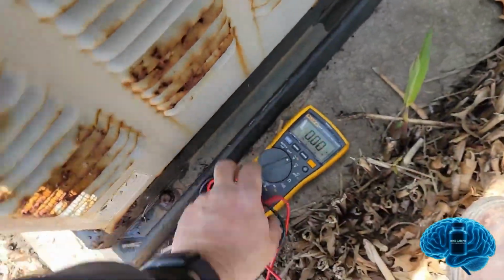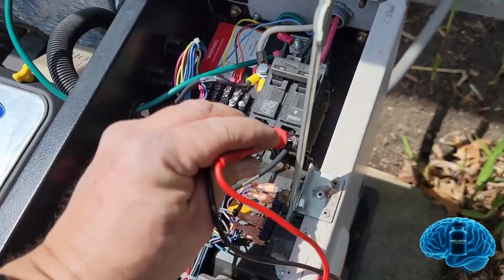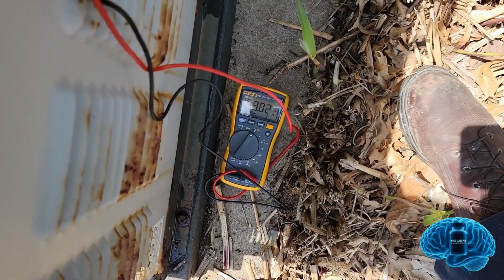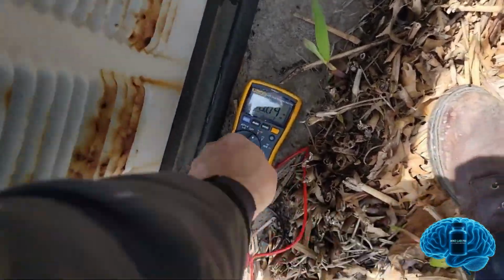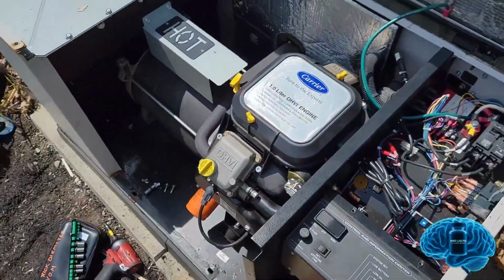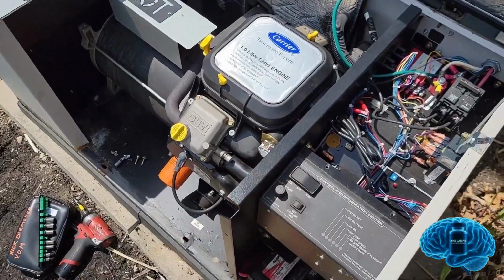I'm going to put that down here, see if we can get an accurate reading. My Fluke 87V doesn't do that. We're still running 58 hertz, which under a load it probably is going to modulate. There's nothing I can do about that. That's controlled by the control board.